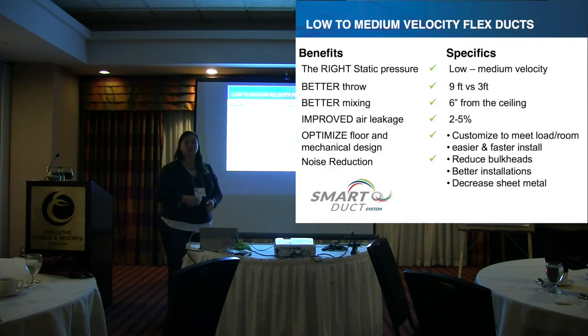Returns. The system's so efficient that you can essentially use one return per floor and just undercut the door by an eighth of an inch per diffuser head. Some builders still want to use traditional returns, one per room, but this is the opportunity to take a step back and say, all right, we're using a more efficient system. If we put the low wall return and high wall return in the right place, centrally located, we should be able to switch over.